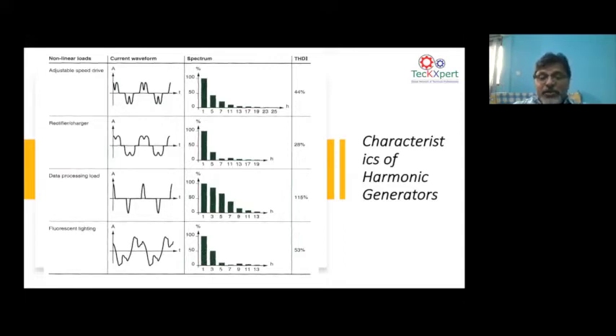Now, if you look at this 3rd harmonic, ultimately what happens with it? This 3rd harmonic finally flows through your neutral, because everybody knows the 3rd harmonic has a phase sequence which goes in line with the line voltage and line currents. So it is in phase with the line. That means ultimately when it all comes to the neutral, this is a balanced extra current. That current naturally flows in the neutral. And so the neutral conductor will ultimately carry these 3rd harmonic currents. Go to the next.